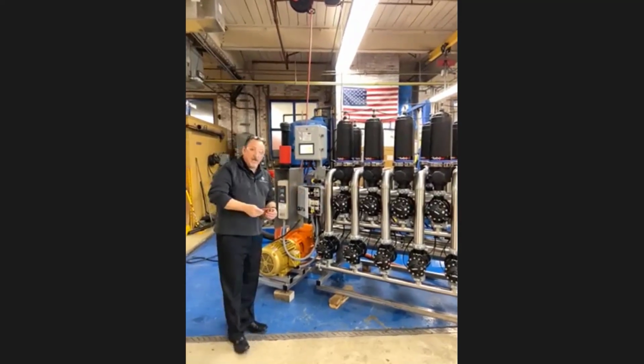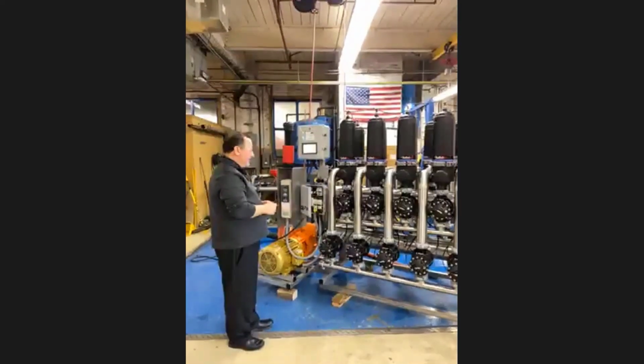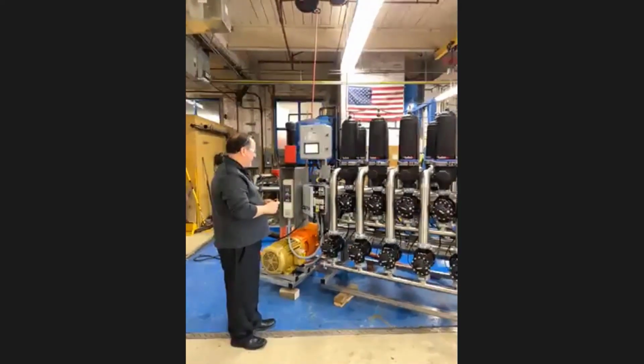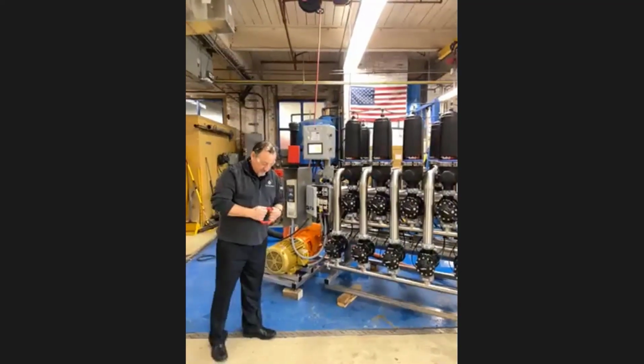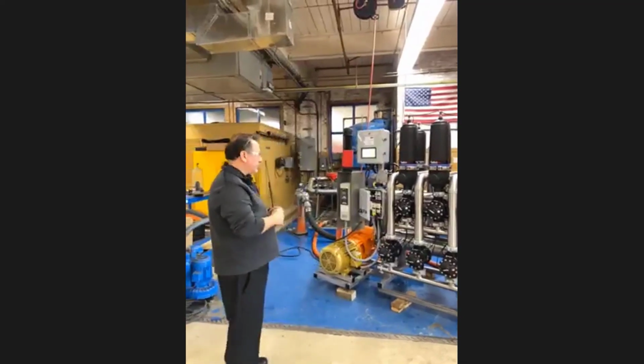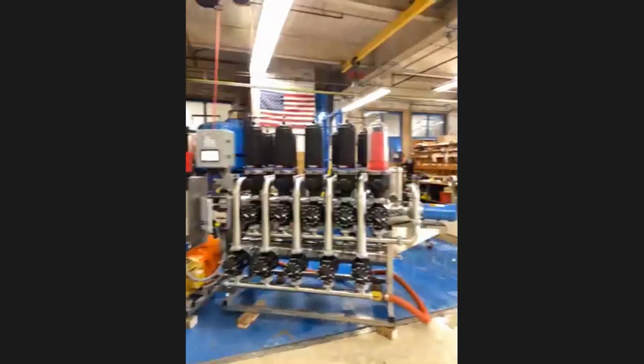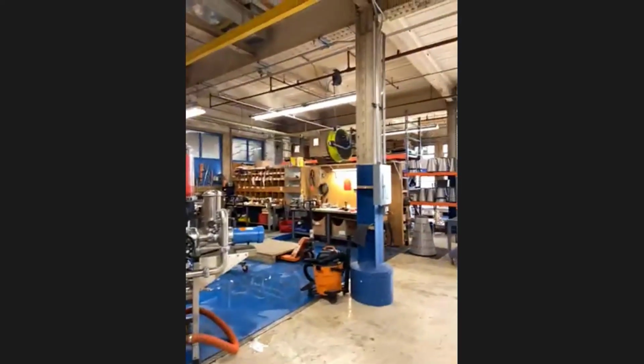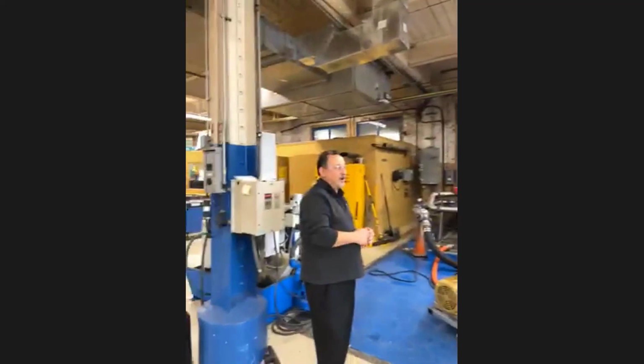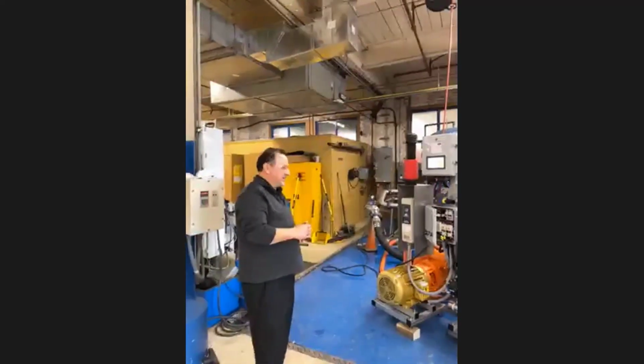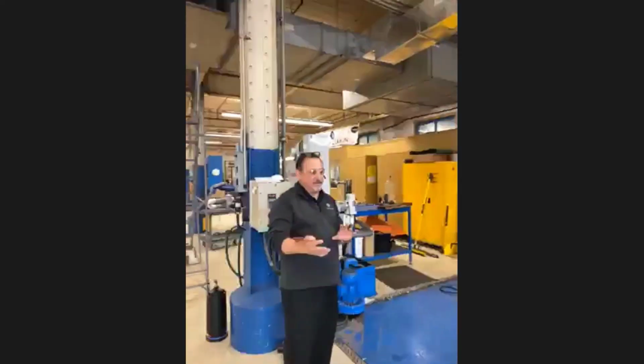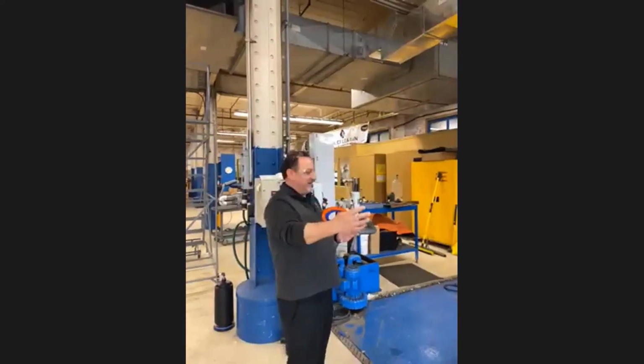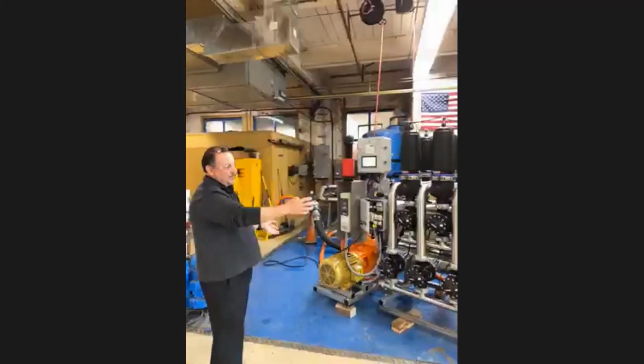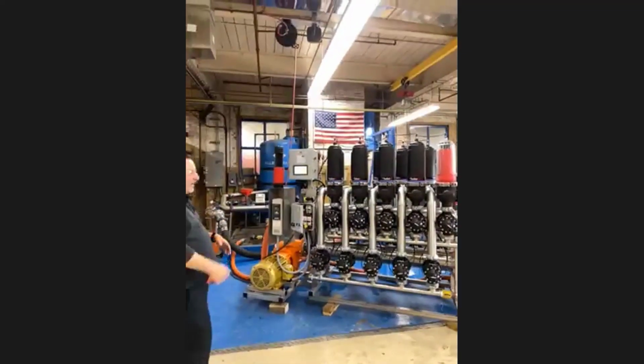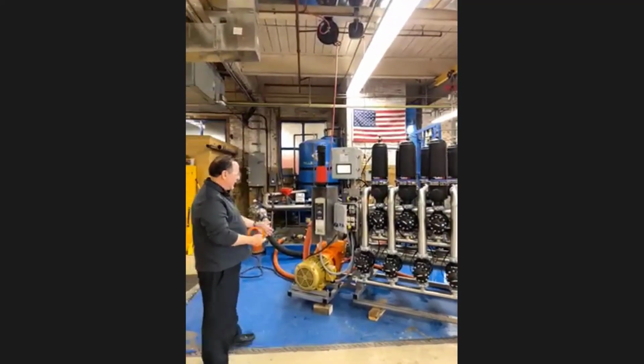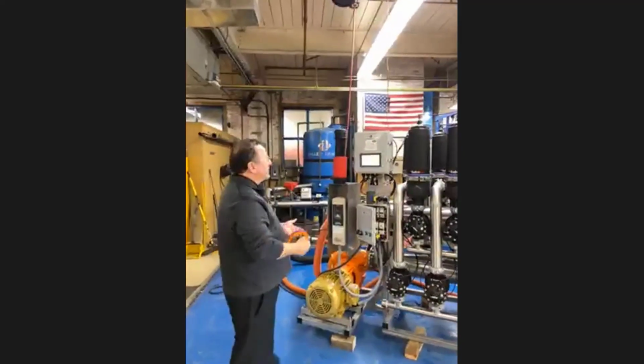You're kind of pre-answering questions now, David, because that was one of the questions. Is this setup typical of an installation with lots of pods, or is this a test stand? What is typical? So thank you for answering that. Another question that did come in is, does this system come with a VFD standard on that primary pump? On this one, it was requested to do a VFD standard on the primary pump, but again, we've already done studies on what's the most efficient, whether to use a VFD pump or the way we have it. The way we have it, with a low head pump running 60 hertz and the booster pump only coming on during a backflush, is very efficient. Because if we wanted to run this at a lower amp draw, then lower hertz, in turn the flow rate wouldn't be 1,000.